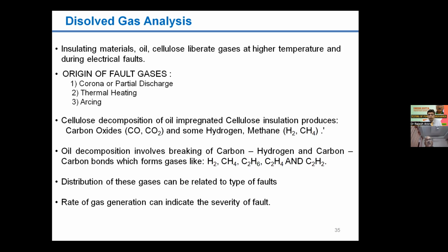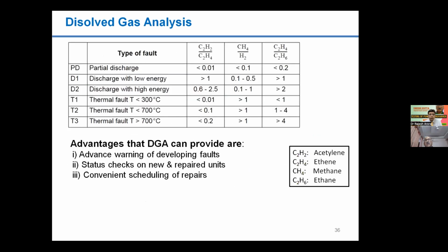Maybe what kind of fault is there inside the transformer. Whether the fault is with the core, or with the winding, whether some copper involvement is there. So different types of faults occur in different temperature regions. That kind of information may be derived if we see the DGA as well as the electrical tests simultaneously. So DGA is very important if we want to arrive at a conclusive result on what kind of issues have taken place. Next.